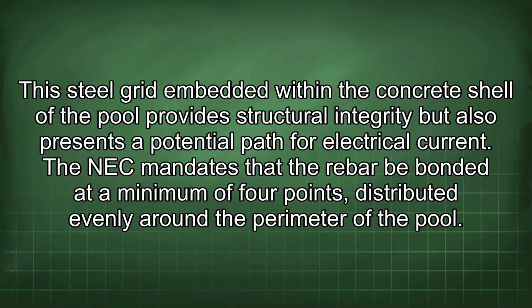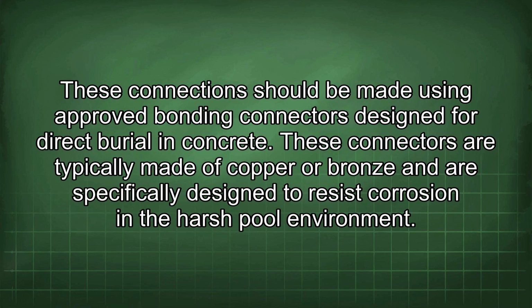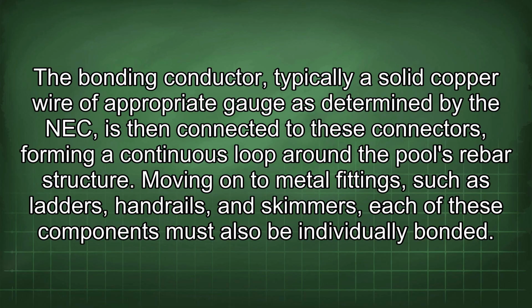This steel grid embedded within the concrete shell of the pool provides structural integrity but also presents a potential path for electrical current. The NEC mandates that the rebar be bonded at a minimum of 4 points, distributed evenly around the perimeter of the pool. These connections should be made using approved bonding connectors designed for direct burial in concrete. These connectors are typically made of copper or bronze and are specifically designed to resist corrosion in the harsh pool environment. The bonding conductor, typically a solid copper wire of appropriate gauges determined by the NEC, is then connected to these connectors, forming a continuous loop around the pool's rebar structure.